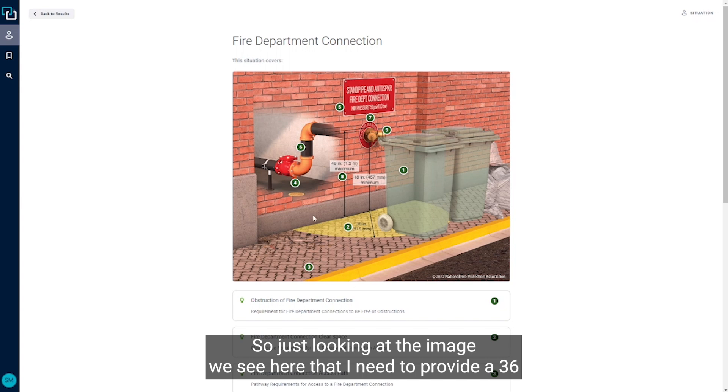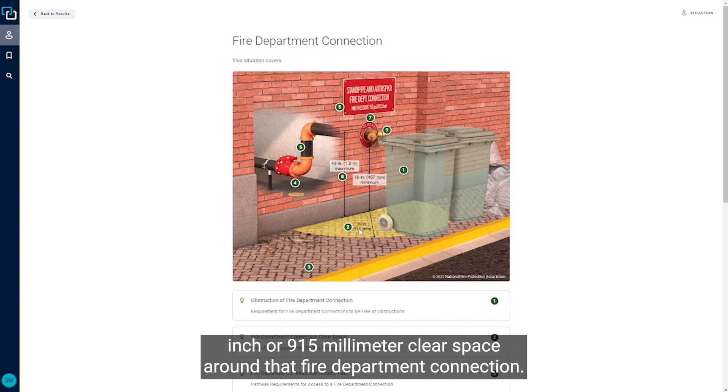So just looking at the image we see here that I need to provide a 36 inch or 915 millimeter clear space around that fire department connection.